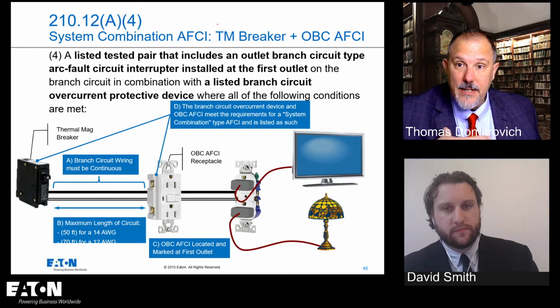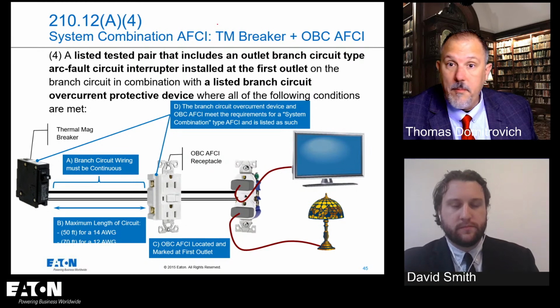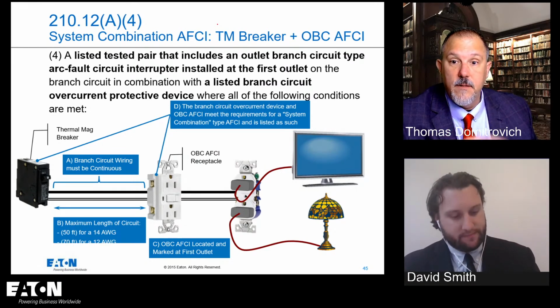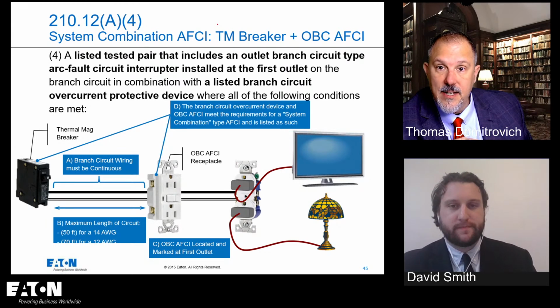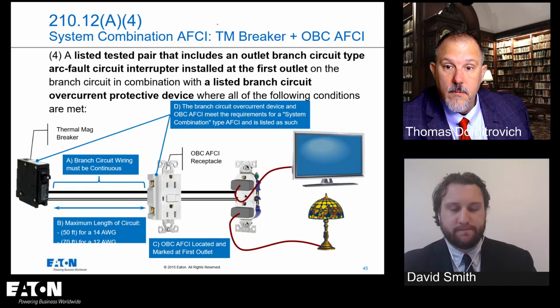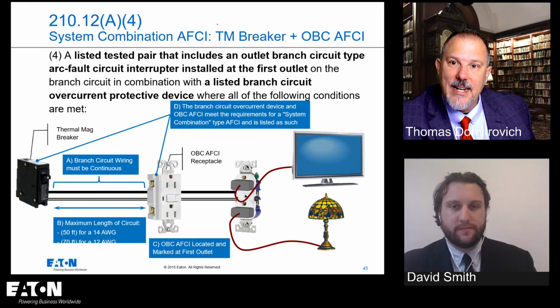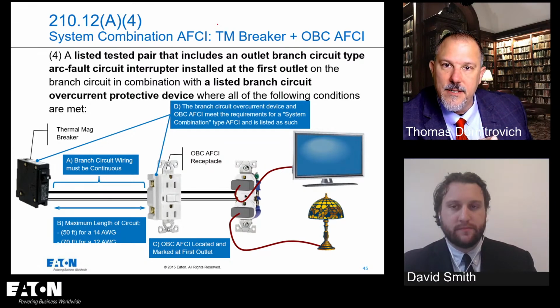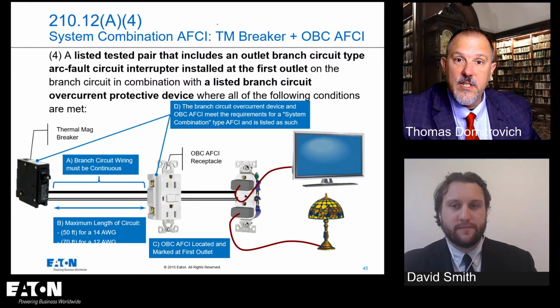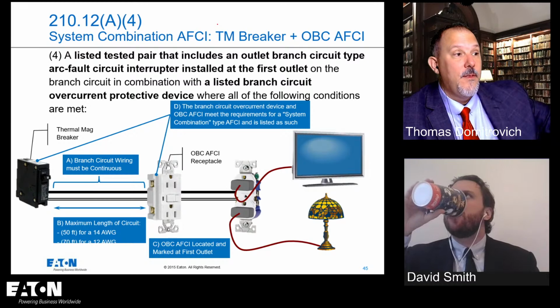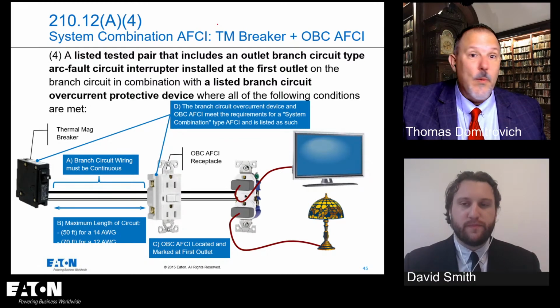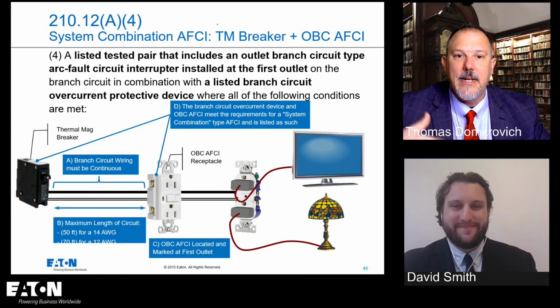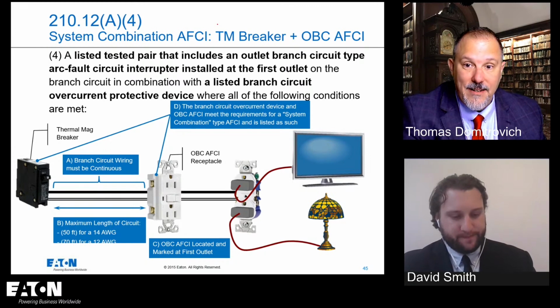Now, what we did about 3 years ago was we made one. We made a listed device that's paired up with the OBC AFCI. They ship together. And they're listed to UL 1699 because they tried to make a standard for this, and it never passed ballot. There were multiple tries. But what was occurring was there was a faction of individuals that wanted to reduce the level of protection that was currently afforded. The code panel says we want to do that. The STP said we didn't want to do that, but because of the mix, we didn't get enough votes to actually create the standard.